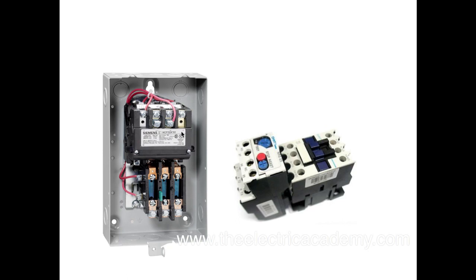This is where your overloads will go, there's your overload reset switch. In here is your coil and probably one of a few of these that have to really look at the nameplate. This will be your holding contacts up here, probably these two. Actually, this will be your coil and your holding contacts will probably be somewhere up in this area.